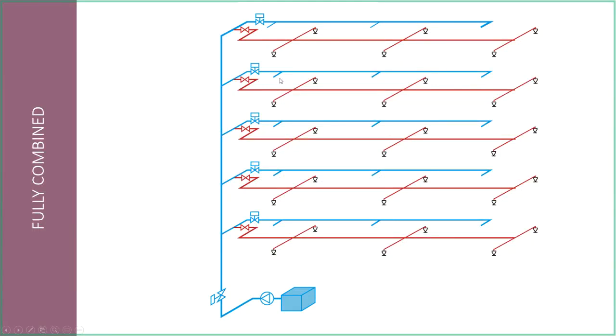So what that does is that when the sprinklers operate, those priority demand valves will close, and that will mean that people can't use the domestic water whilst the sprinklers are activating. And that just ensures that all of the water is available for the sprinklers, and it means that the pump is just doing basically one job at a time. It is supplying the water for the sprinklers.